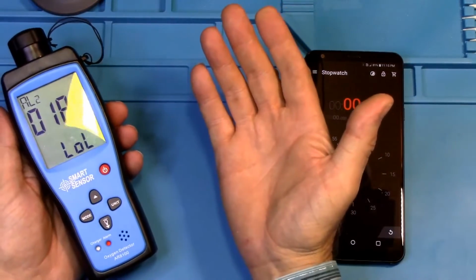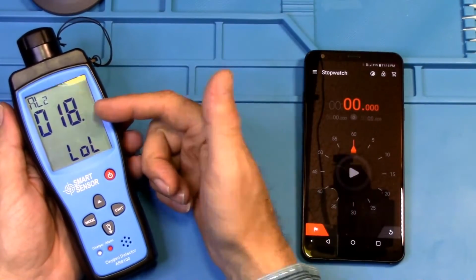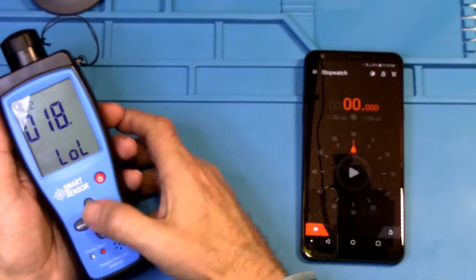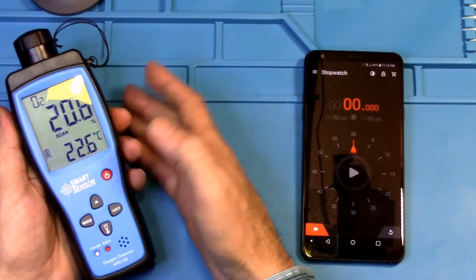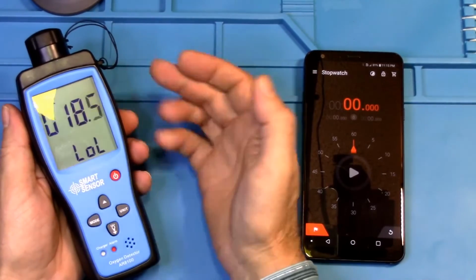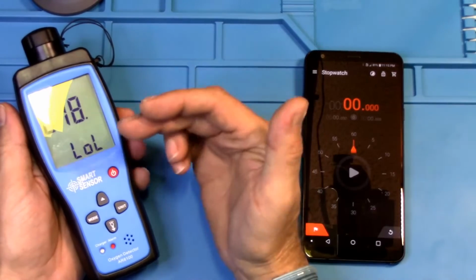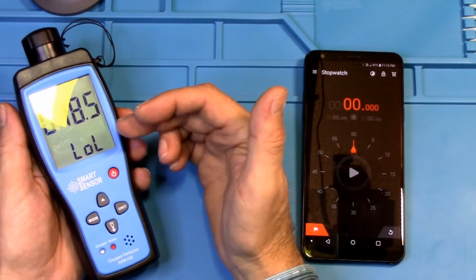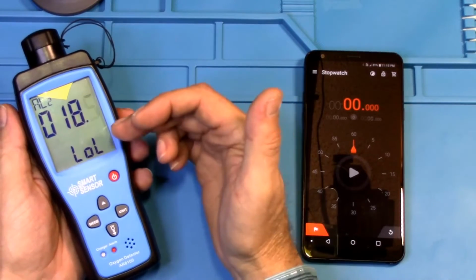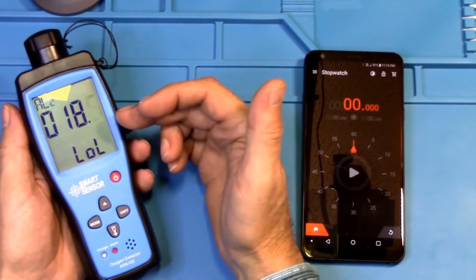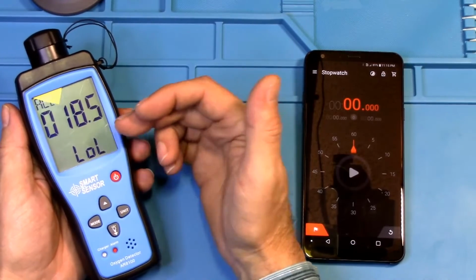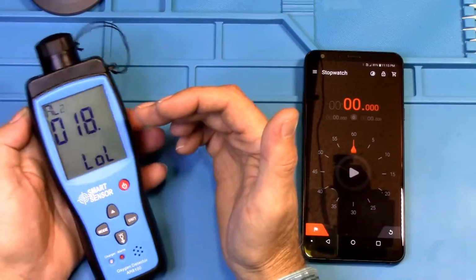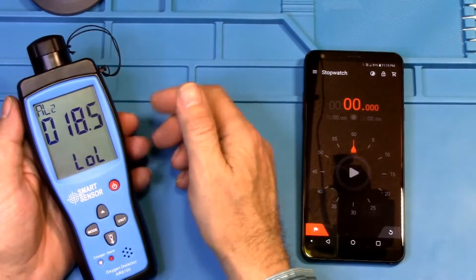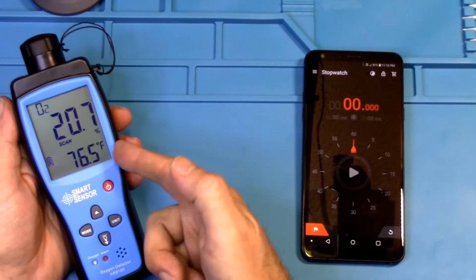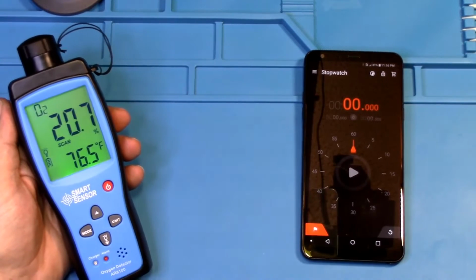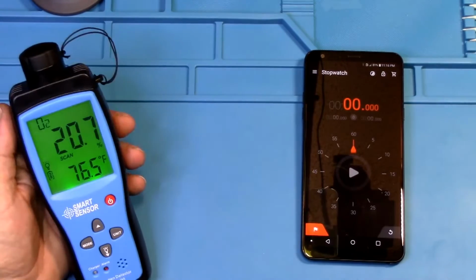See, I really don't see the point of that, because once it gets to 18.5, it's going to alarm. It's going to alarm before it ever gets to 17. What I thought was going to happen was at alarm 2, you would be able to set it to, say, 25, because you don't want your levels to go above 21 either. No more than you want them to go down. You don't want too much oxygen. Too much oxygen can be, I would say, just as deadly probably as not enough oxygen. So I was hoping that there was a high level. When you hit the unit button, it changes the Celsius to Fahrenheit, and the down arrow is also a backlight, which is very nice.